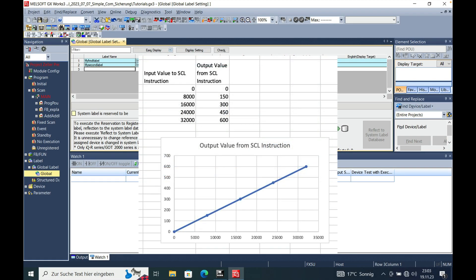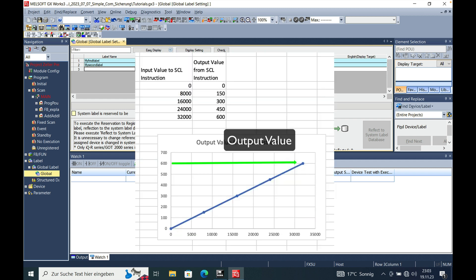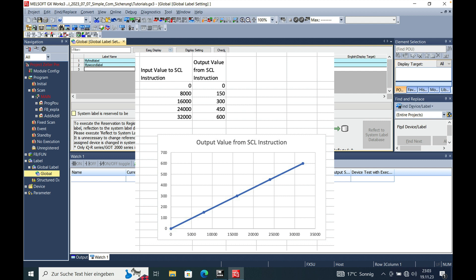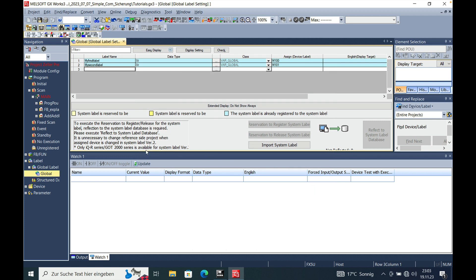Why do you need a scaling function? A scaling function is used to calculate a certain input range to a predefined output range where you can change your value, let's say from an analog input module, for example the FX5 4AD where I already made a video. And this card gives you a value from 0 to 32,000 units using 0 to 10 volts respectively 4 to 20 milliampere. And there is a function in the GXworks where you can actually predefine this value.